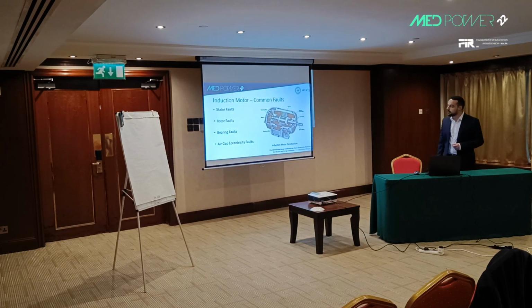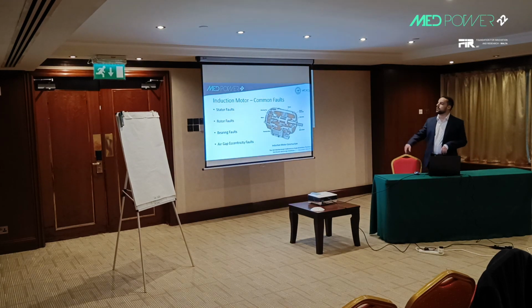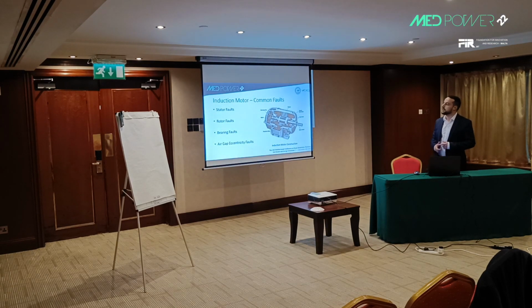So the main motor used is an induction motor, as seen here. Although it is very robust, with a simple construction, faults may develop. Here are the main faults that can develop in the induction motor, namely stator faults, rotor faults, bearing faults, which is the most dominant fault of the induction motor, and eccentricity faults.